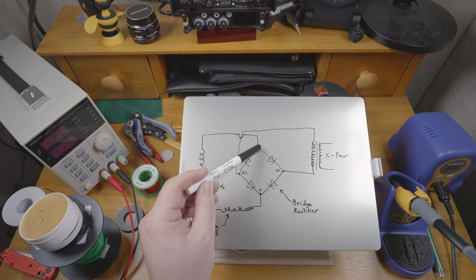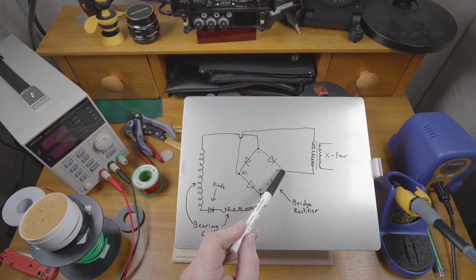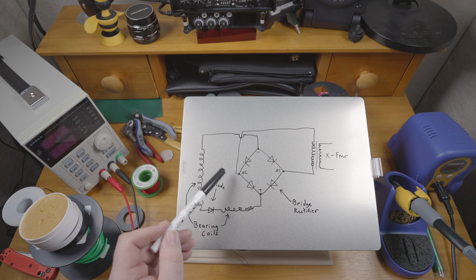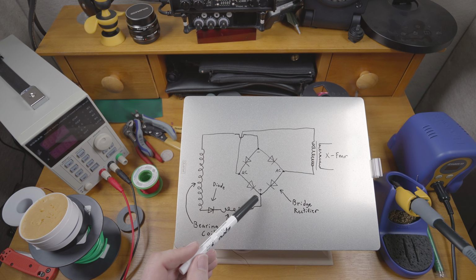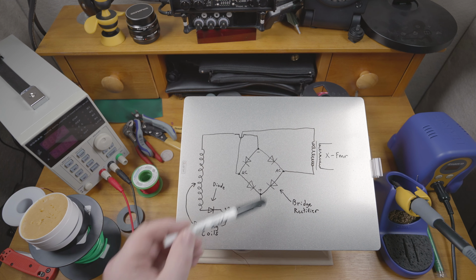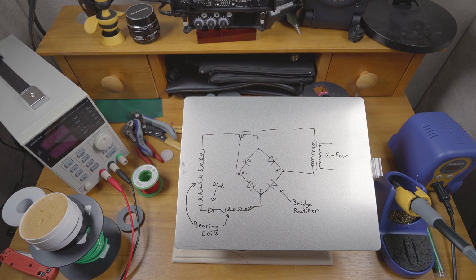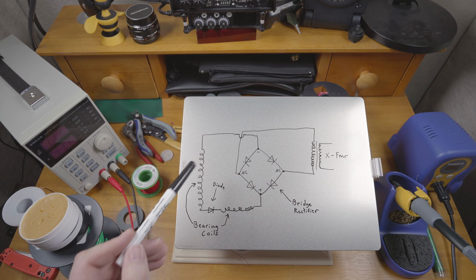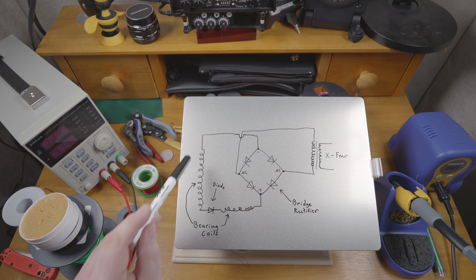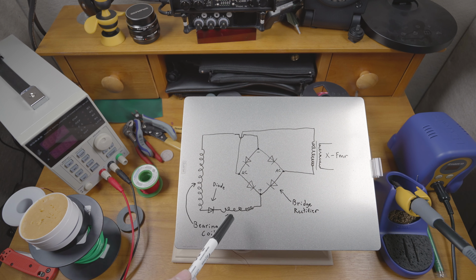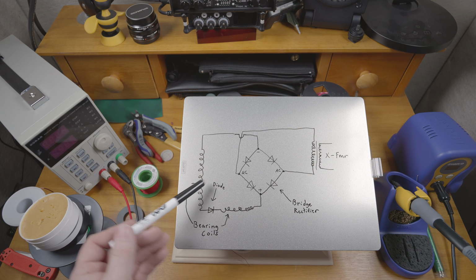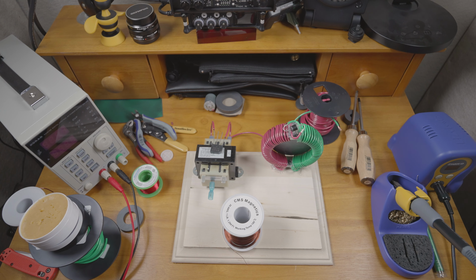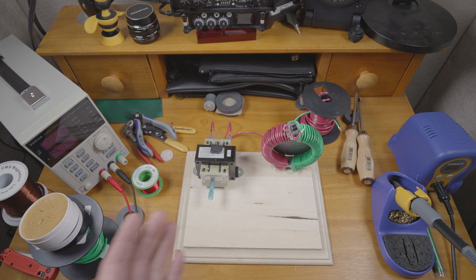This current going this way passes through both diodes, making both terminals the same potential, so no current flows through our transformer winding, but that current continues on through these two diodes and ends up back here. So this would just be a complete short circuit. Depending on the polarity of this diode, based on how they wired it, it would either completely block all output from this winding or completely short this winding out, once again preventing any output. So the addition of this rectifier, wired this way, guarantees this device cannot produce power, as if there weren't enough issues already.